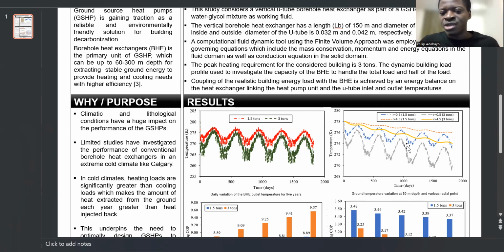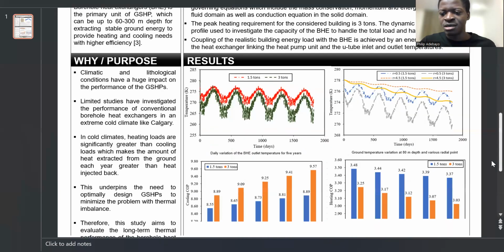Though if we look at the case of 1.5 tons, it's much better than the case of 3 tons, but there's also the possibility that if we continue to use this system, it will also get to a point just like where the 3 tons case is at the end of the 5-year period. So it's still better off at the far end, especially for the 1.5 tons at the radial distance of 4.5, and also for the 3 tons at the radial distance of 4.5. It is not as bad as around the borehole area, which is majorly our concern to avoid ground freezing.